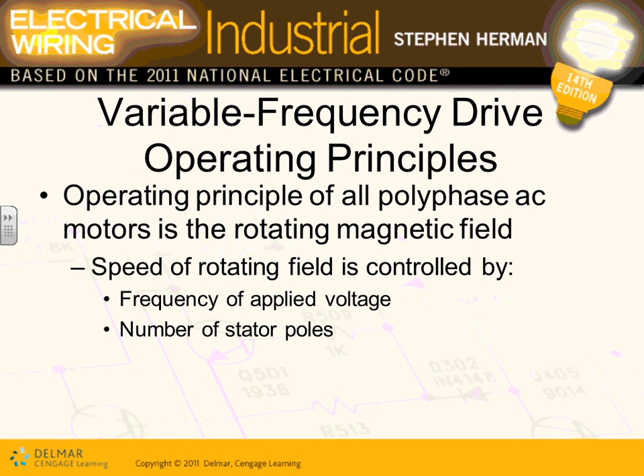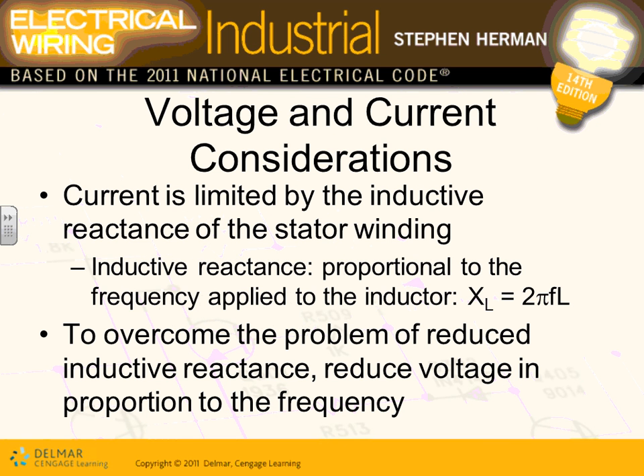So they take the AC and start altering the frequency and the voltage, and apply it across the motor at different frequencies and voltages. By altering the frequency and the voltage, they can speed control the motor. And that's exactly what I love. They can run it forward, reverse, at almost any speed I want between synchronous speed and 15 RPM or 30 RPM. So that's where it talks about the voltage considerations.